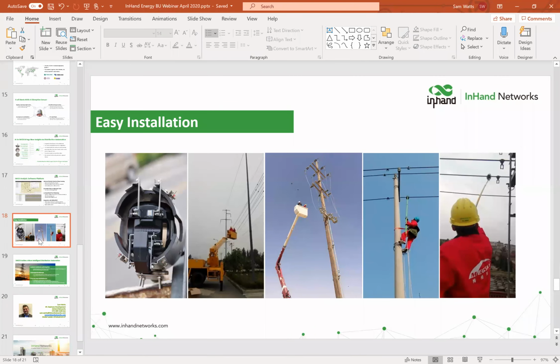These are easy to install. The current version of the sensor does need an installation jig that's very lightweight, which we provide for free. It clamps around the sensor, opens up the hook, and you push it onto the energized line. What we've found is the bucket truck method works very well, and half the time you don't even have to use a hot stick—you can just take the tool and put it up.